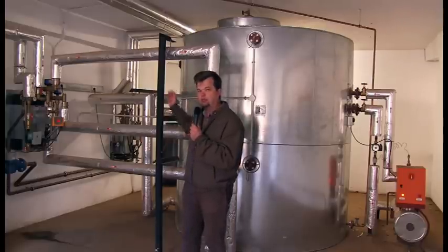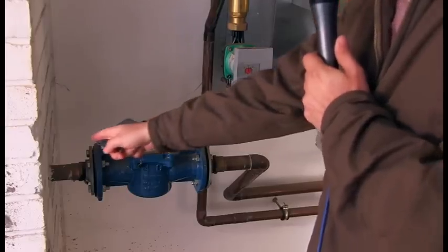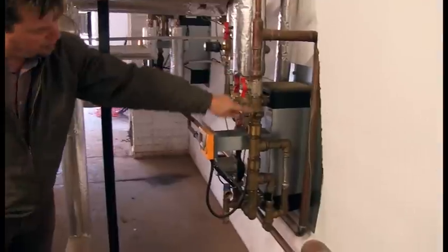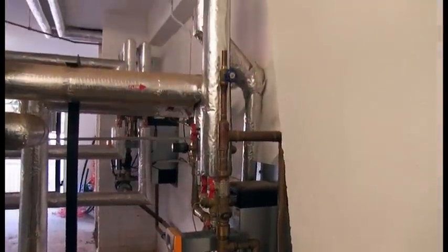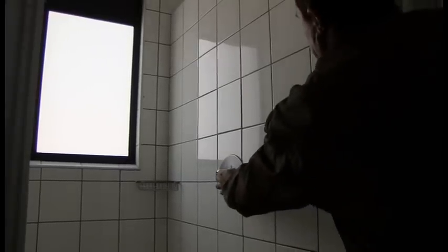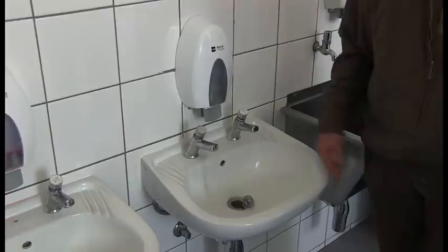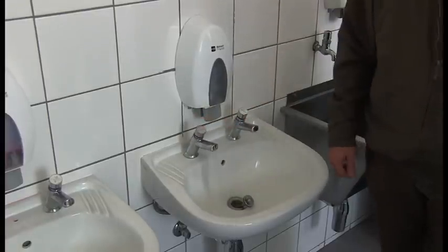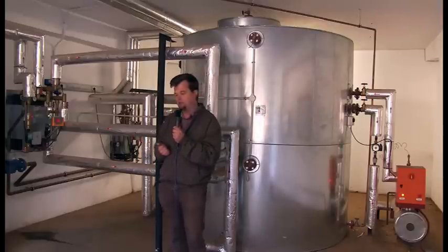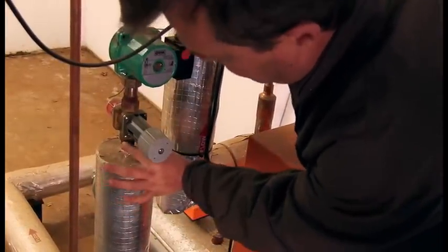On the discharging side we have what we call a fresh water station. Cold water comes in through a water meter to measure student consumption, then goes through a heat exchanger, instantaneously heating the water loop into the building. In the bathrooms we have low-flow shower heads and taps. These taps are timed — when pressed they run for about 30 to 60 seconds, consuming little water, so you cannot accidentally leave a tap open or dripping.